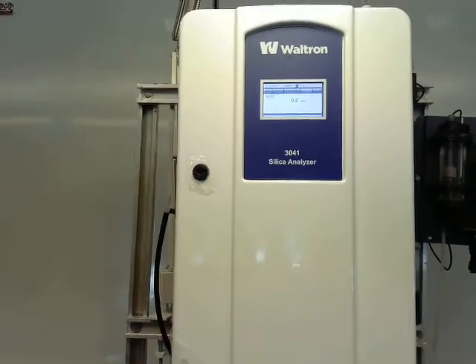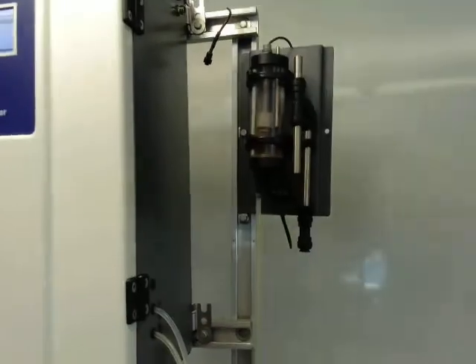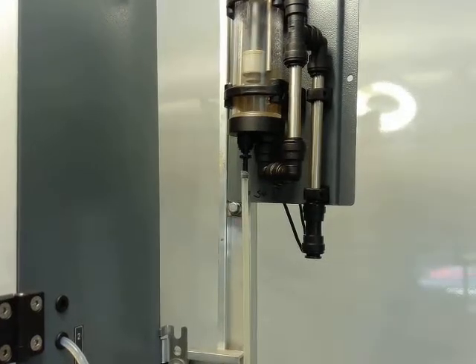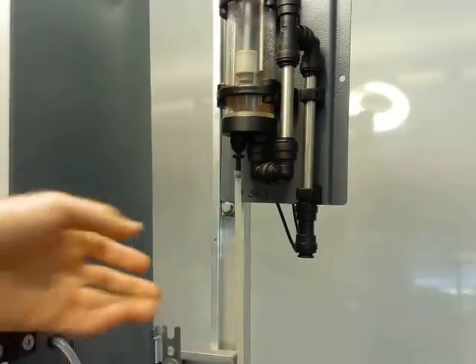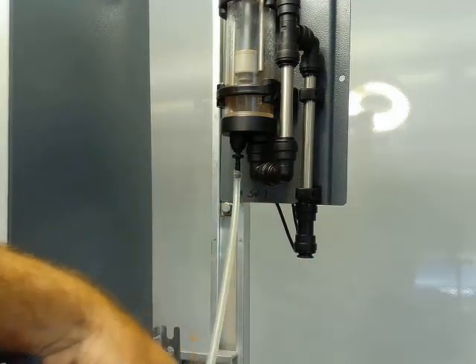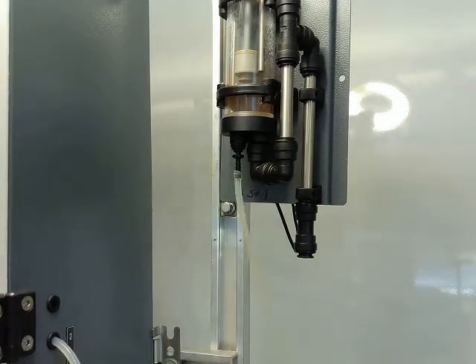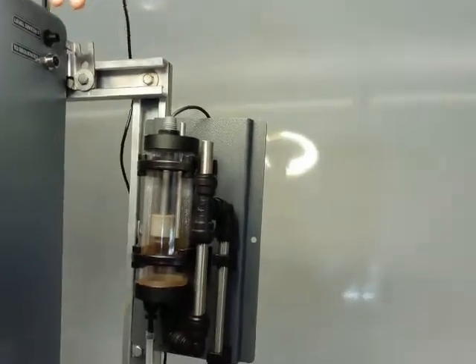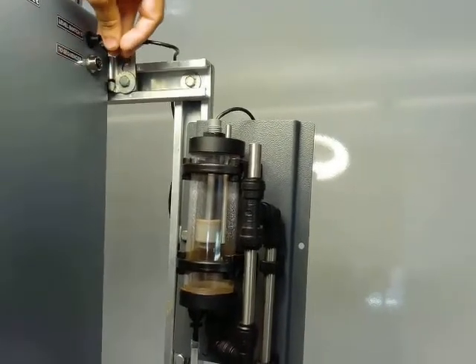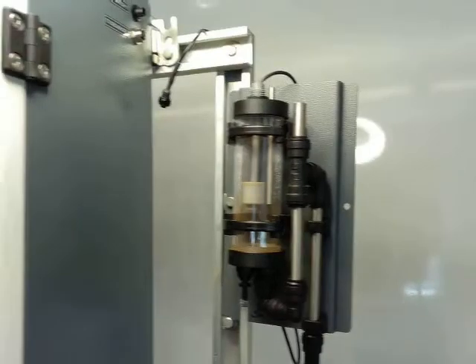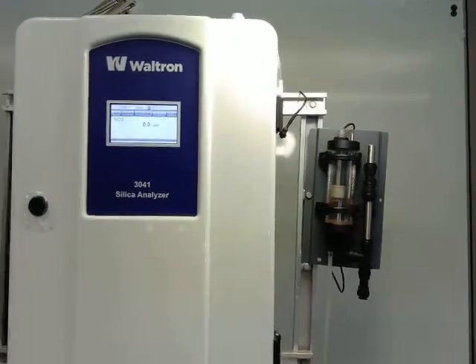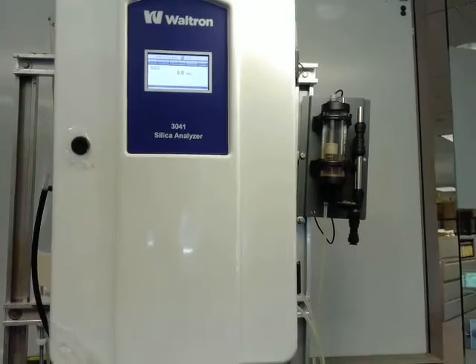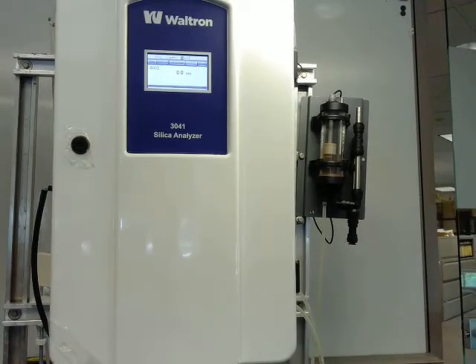So now we're in front of the analyzer. The first thing we'll look at is on the side here. That's the fast loop reservoir that has our sample come into. On the bottom side here, this will be the tubing that goes to our analyzer, and that's where the analyzer will draw its sample from. On the top here, this will be our connection to the analyzer. Once we plug this in, we'll get our flow alarm should there be no flow to the analyzer. Right now I just have it disconnected because we don't have a live flow in our conference room here, so we would trigger the alarm and not be able to run calibration like we want to.